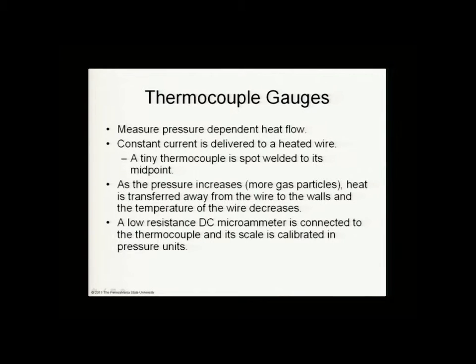If you remember our table from about 5 or 6 slides ago, this is good in the low vacuum range and just getting started into the high vacuum range. It's a very simple piece of instrumentation. It measures pressure by measuring heat flow. So the more molecules that are around, the easier it is to remove heat from a heated resistor. The fewer molecules around, the more difficult it is to remove heat from a heated resistor.